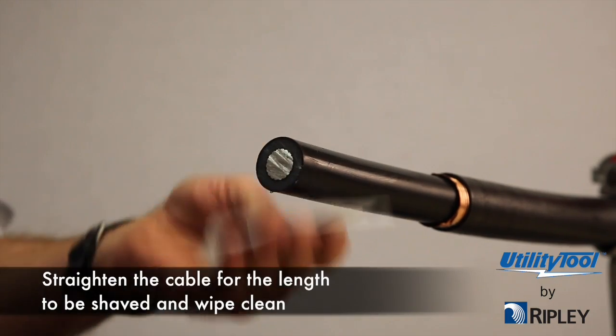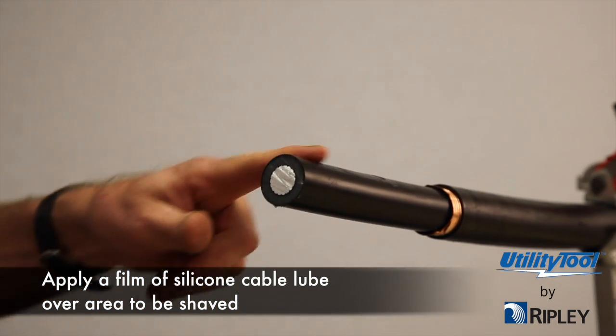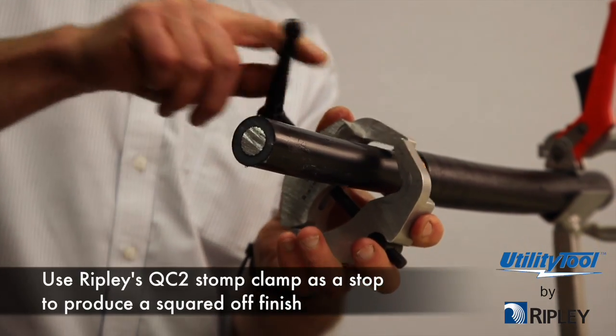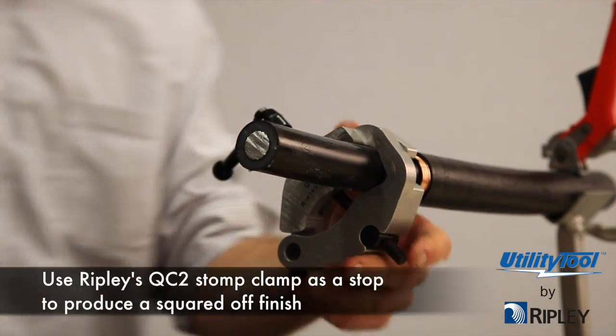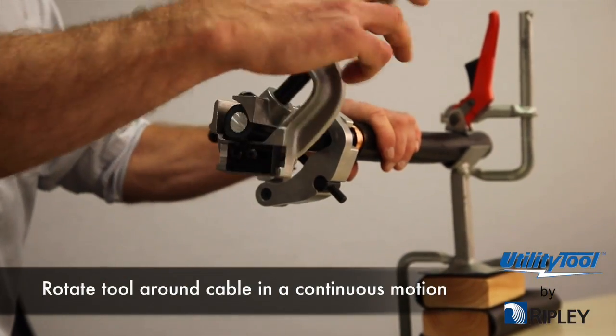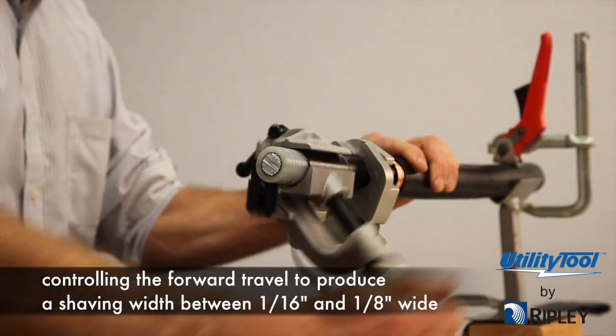Straighten the cable for the length to be shaved and wipe clean. Apply a film of silicone cable lube over the area to be shaved. Use Ripley's QC2 stomp clamp as a stop to produce a squared off finish. Clamp tool firmly over cable. Rotate tool around cable in a continuous motion, controlling the forward travel to produce a shaving width between 1/16th and 1/8th inch wide.